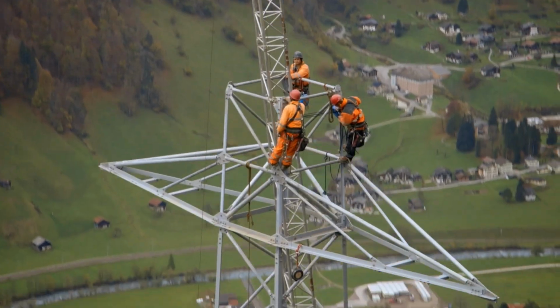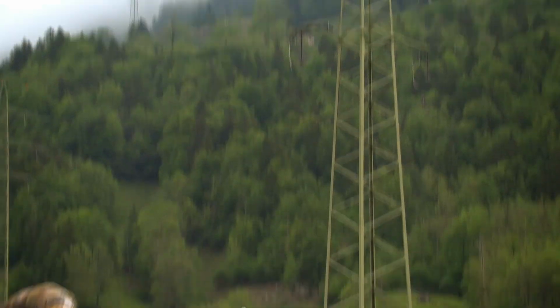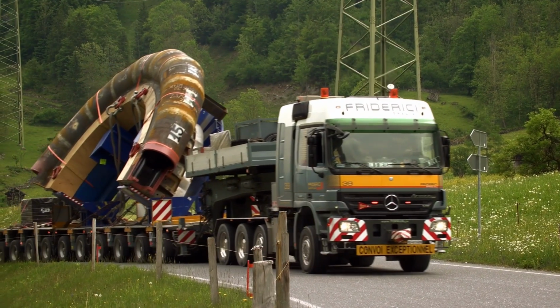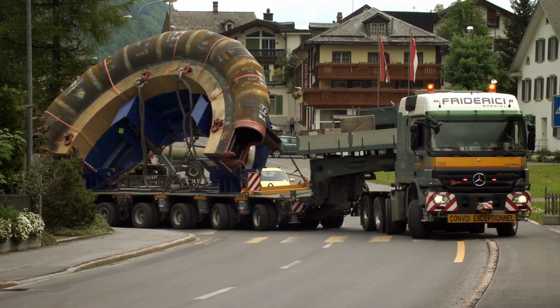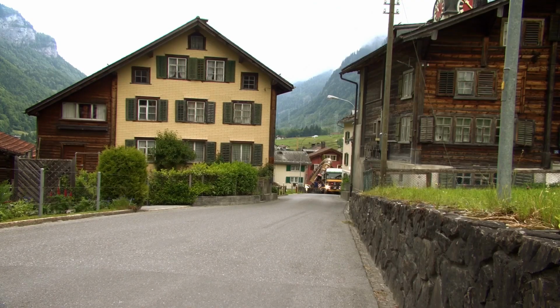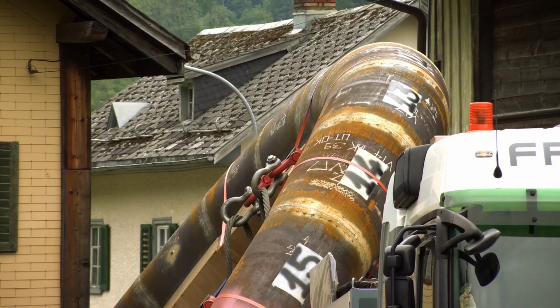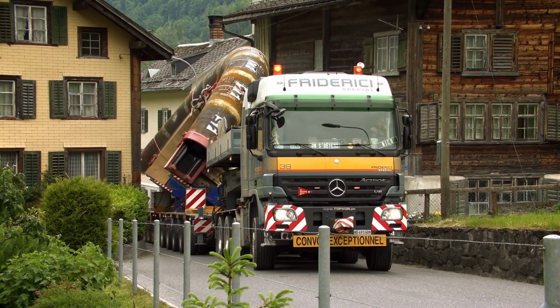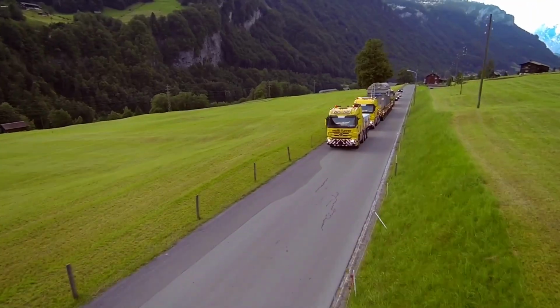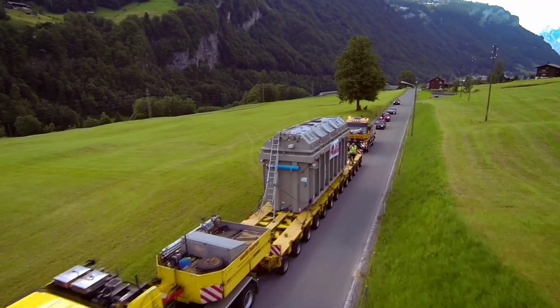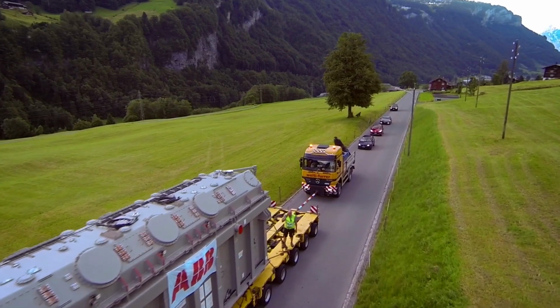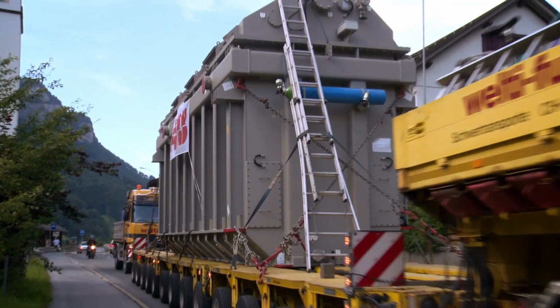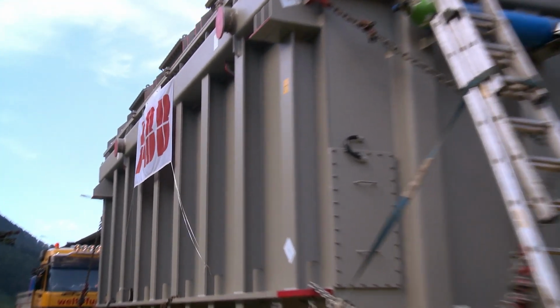While the transmission line was being completed, the heavy equipment transport for the powerhouse was in progress in the valley below. Components such as the spiral casing for the pump turbines were too big to be transported by usual means. At 190 tons, the machine transformers, the heaviest individual items, weighed too much for the 40-ton aerial cableway.